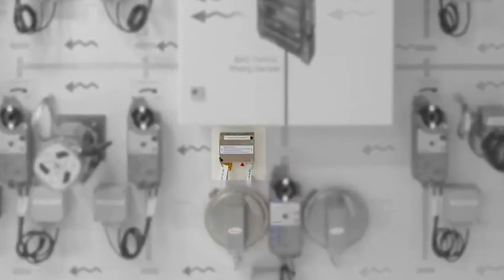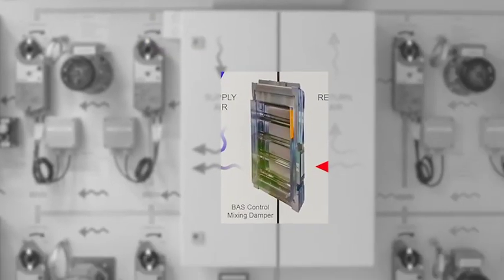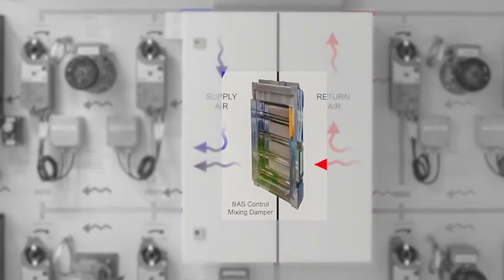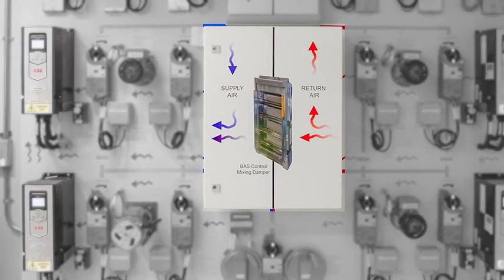The large outlet air main damper is controlled by 3 actuator units. The supply air section has frost thermostat and overpressure switch protection. The system is interfaced with the fire alarm IO unit. This supply section control philosophy is replicated on the return side with an additional BAS-controlled mixing damper permitting recirculation of a controlled amount of air. All AHU control devices are interfaced with the ACS 880 drive units via an interface cabinet.